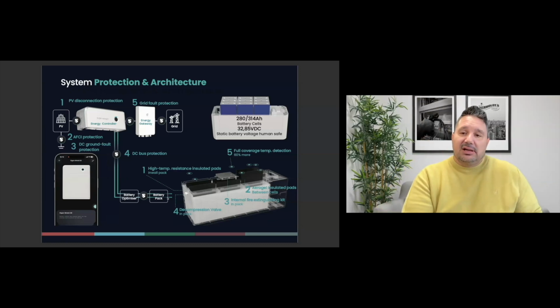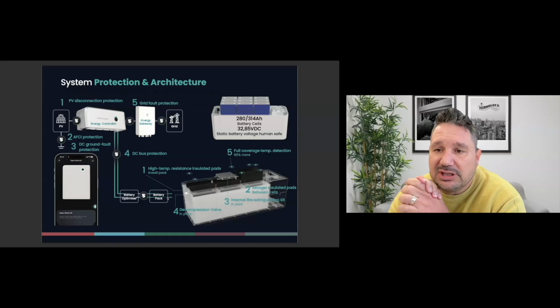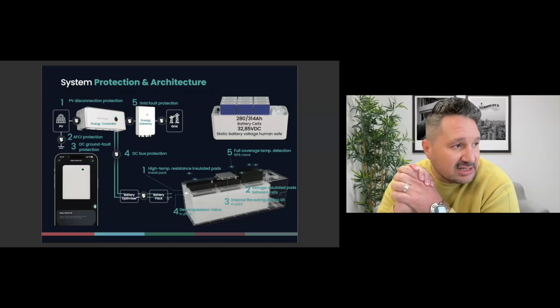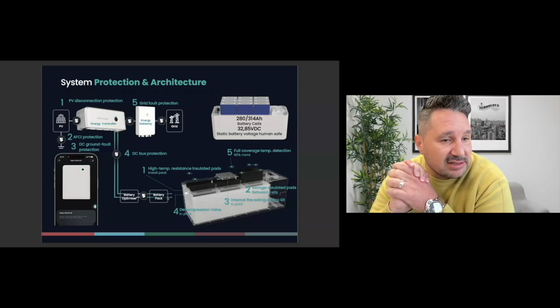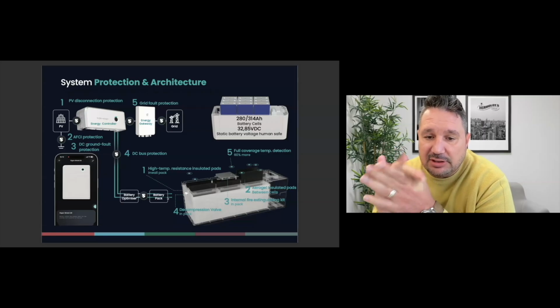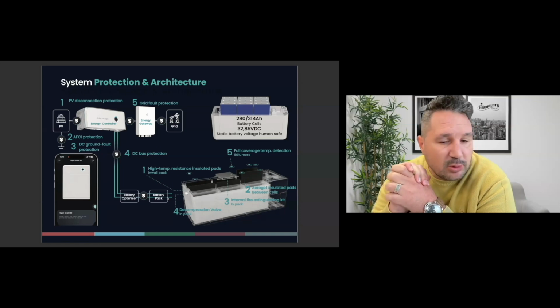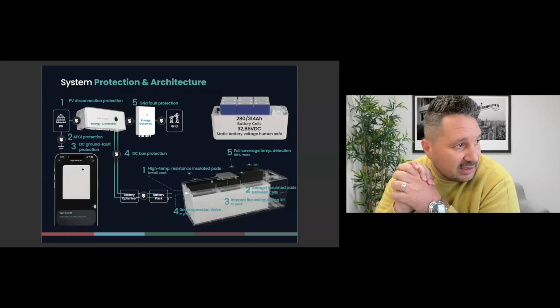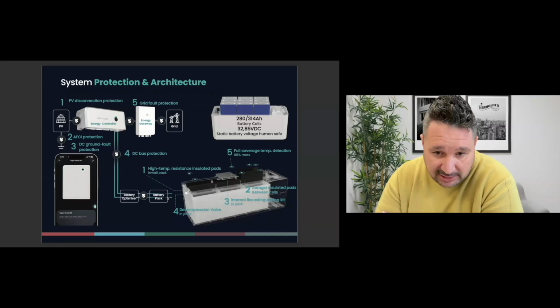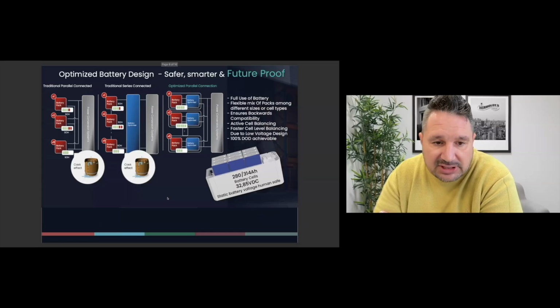Inside your battery packs, they come with 280 amp hour or 314 amp hour cells up to 32 volts. Each battery has a battery optimizer that then boosts the voltage up to 600 and 800 volts. That means that all the batteries operate separate from each other. Inside the battery modules, there are temperature resistance pads on the outside with a battery heater for cold conditions. They can operate from -20 all the way to 60 degrees ambient temperature. There are full temperature sensors across the entire battery module, aerogel insulation pads between each one of them, a decompression valve should you have any gas buildup on the inside, as well as an internal fire extinguishing module inside every single pack itself. This means that you have fire protection on every pack level.